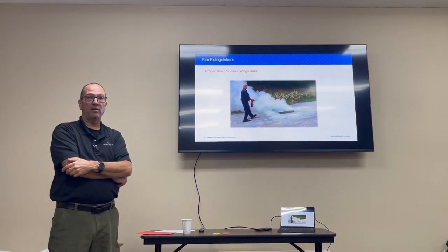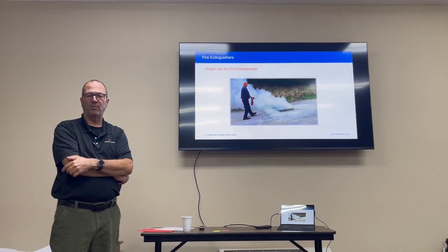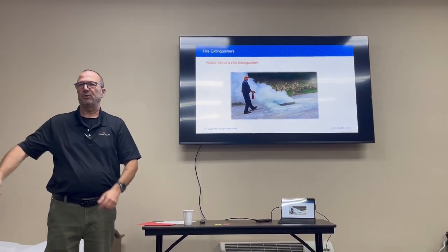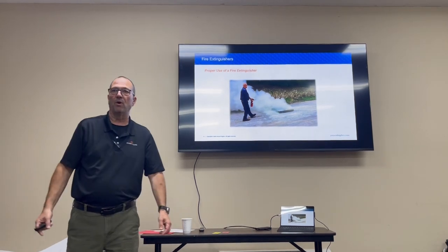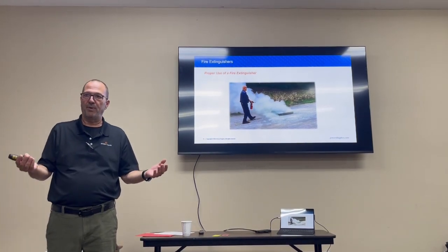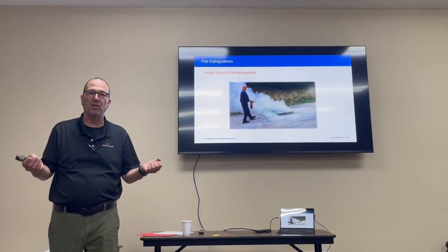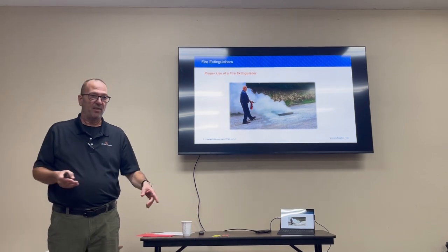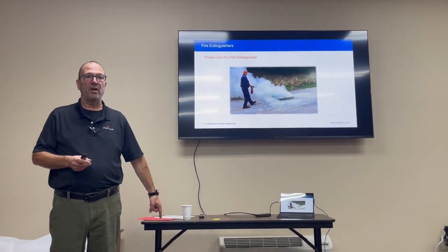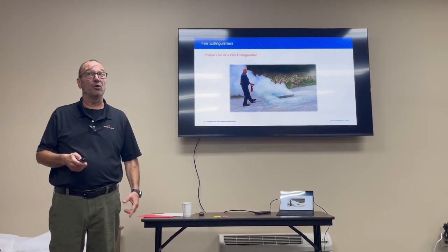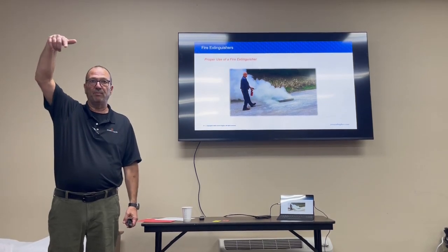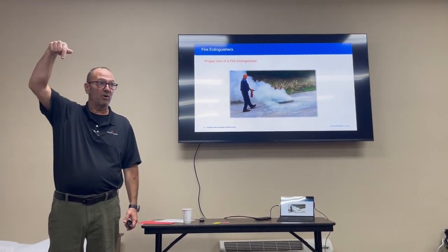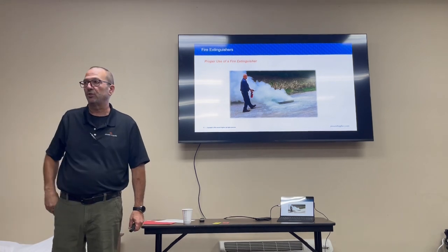I saw it this week on one of the fire drills, the person grabbed an extinguisher from one unit and ran all the way up to unit 6 where we were with a big fire extinguisher and went, oh my God, all exhausted. You don't need to do that. These things are every 75 feet from no matter where you stand because that's code. So they're nearby. If you need to find it, you've got a sign for it with an arrow that says where your extinguishers are.